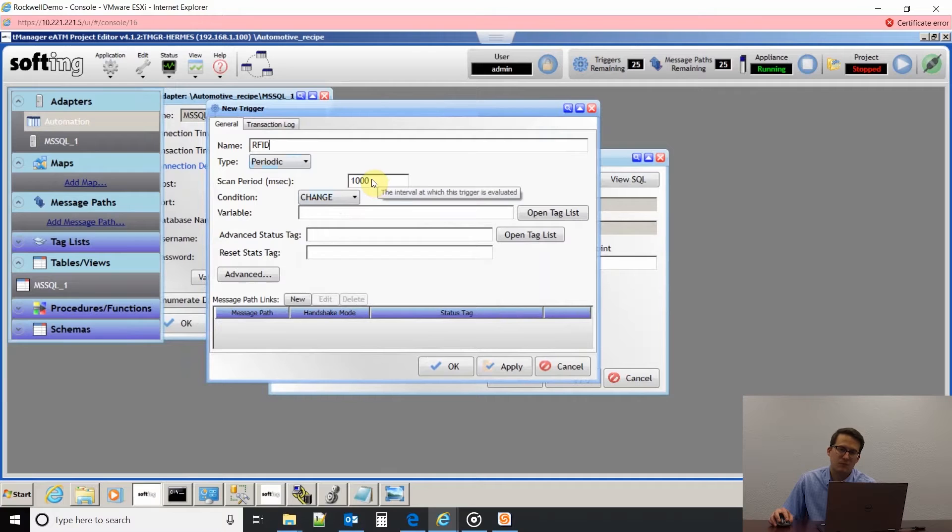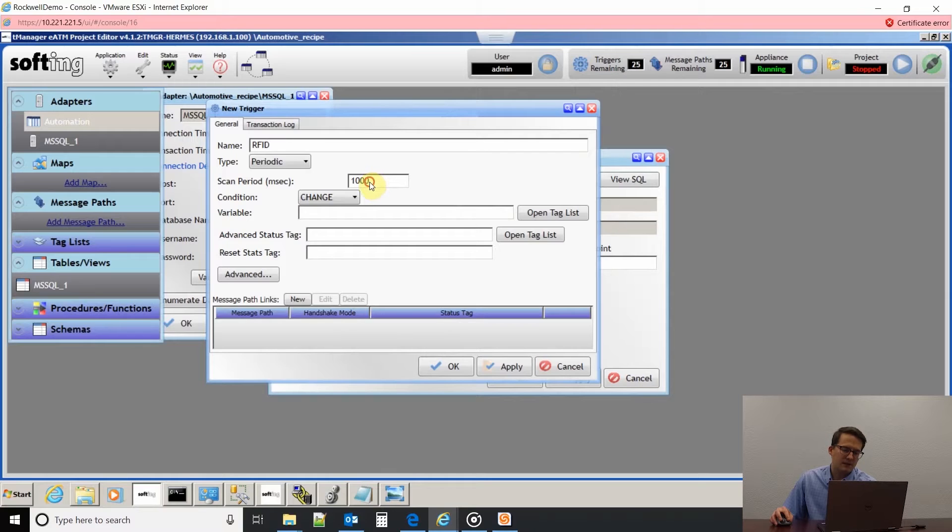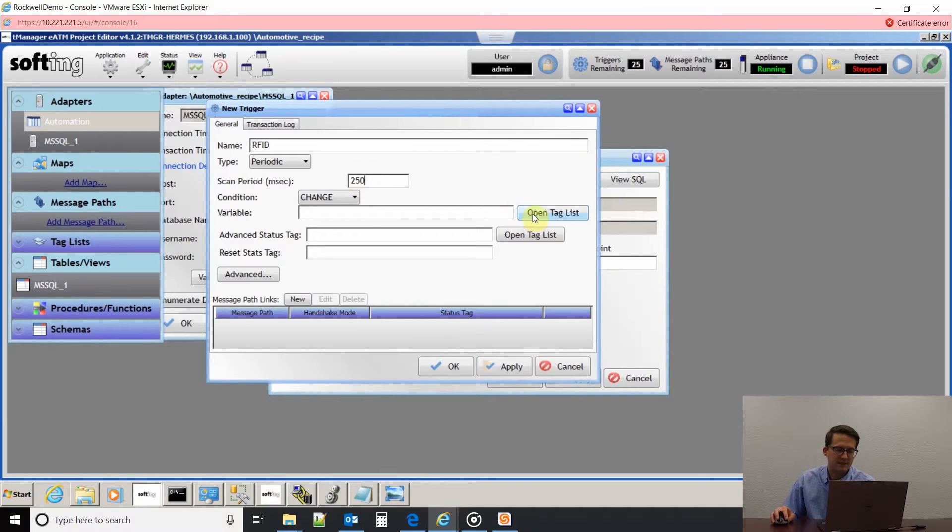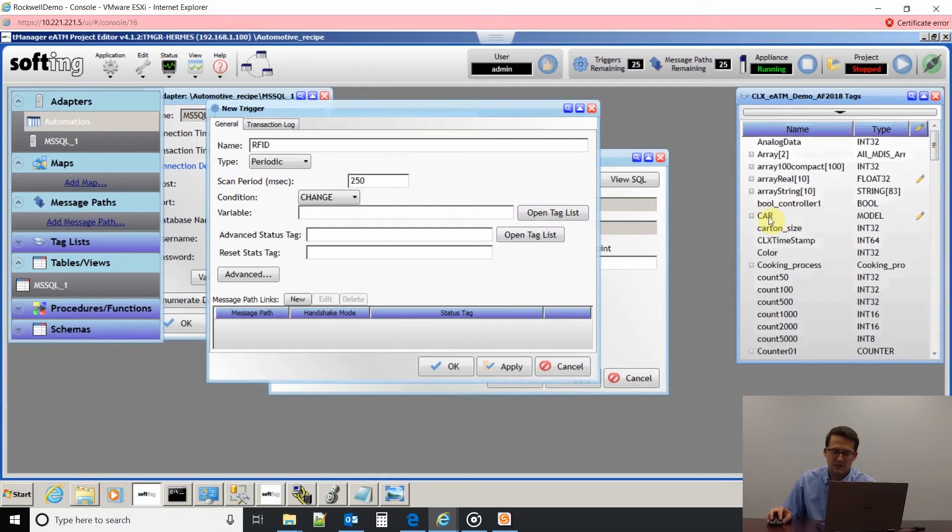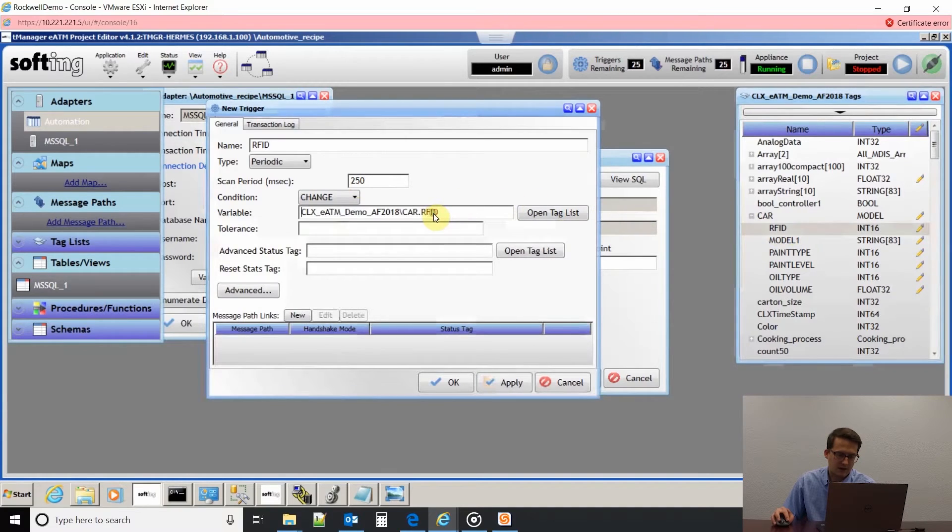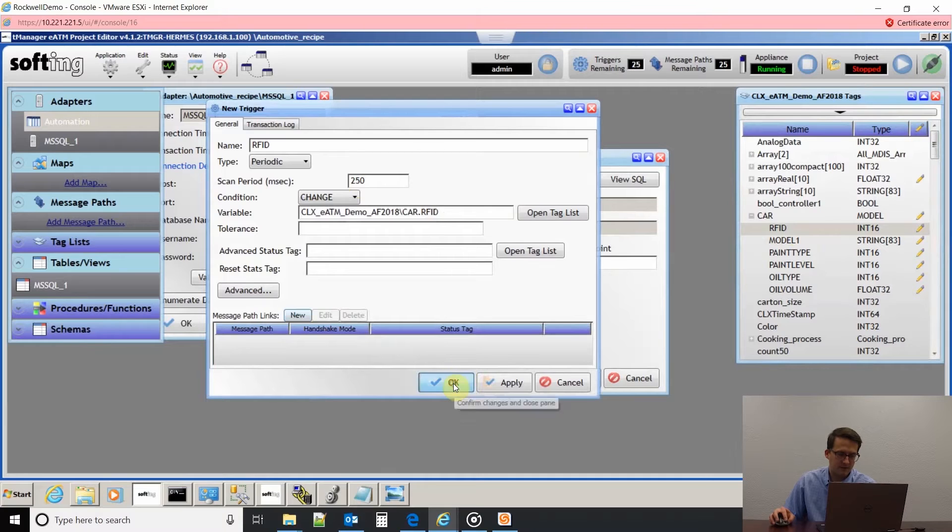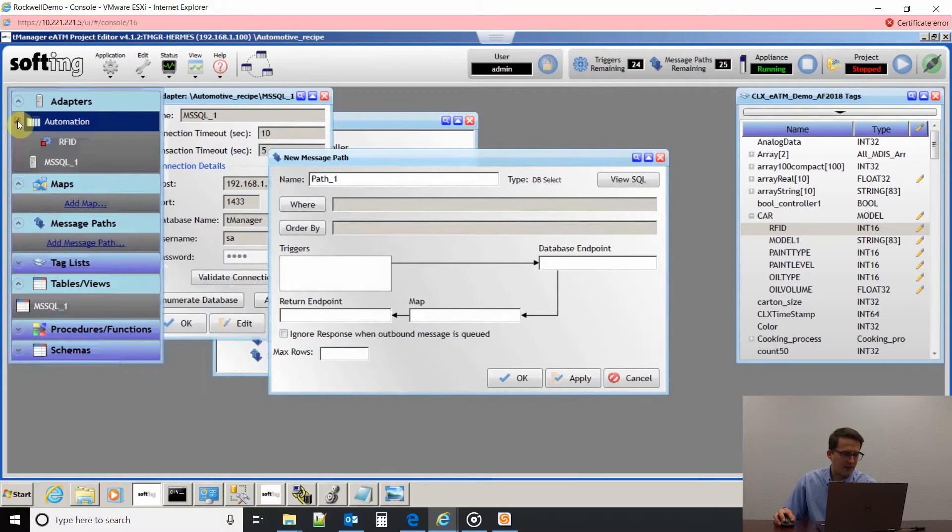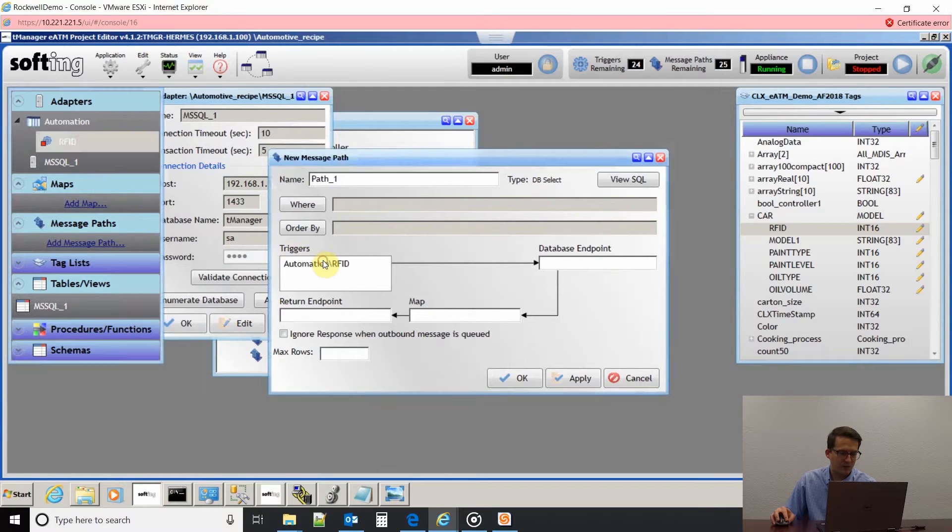If it changes, that's when we'll execute the transaction to pull the data out of the SQL database into the PLC. I'm going to change our scan period to 250 milliseconds. That's the fastest we can scan. If I go and open the tag list, I can pick that ControlLogix PLC. I can see my RFID tag right there and drag and drop that in there. Now that I have that configured, I can grab it and pull it into my trigger pane.